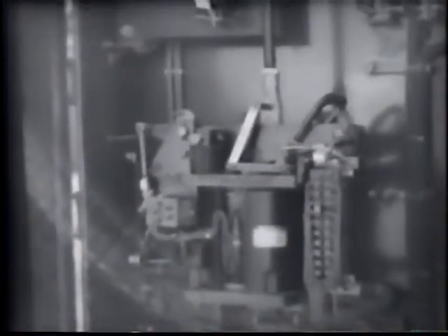This is a view of the operating mechanism of this type of circuit breaker, in which this cylinder right here houses the solenoid that's used to open or close this circuit breaker. Just pull this rod here up or down. And the rest of the mechanism here is some of the controls for this solenoid. We'll get into that at a later session of this class. These terminal boards here house the leads for the current transformers that are mounted on the 69 kV bushings. They come from these conduit here attached to these terminals here. Then depending upon the particular connection that you would desire for the circuit breaker, then you can make your connections to these terminals right along there.